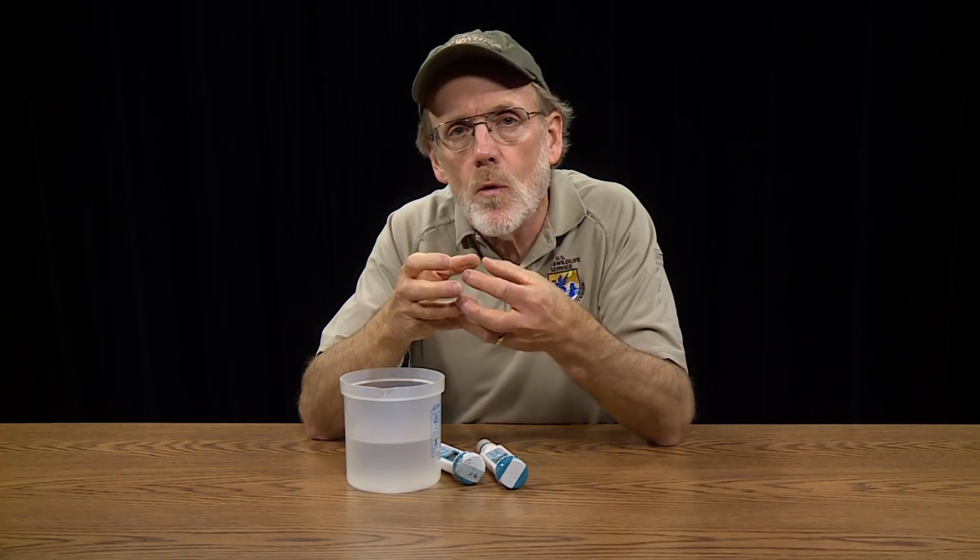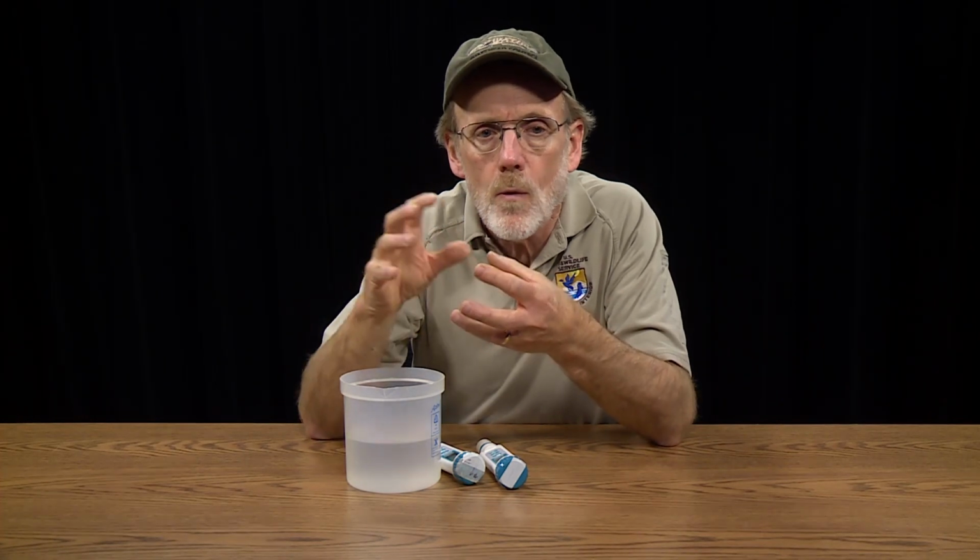Water conductivity is a result of ions in the water, the ion concentration, and temperature. Warmer water has higher conductivity than cooler water. But specific conductivity is after the ionic concentration, so it doesn't want temperature to play a role.